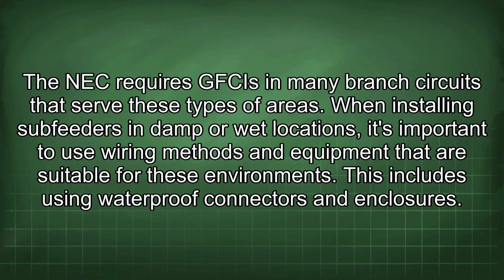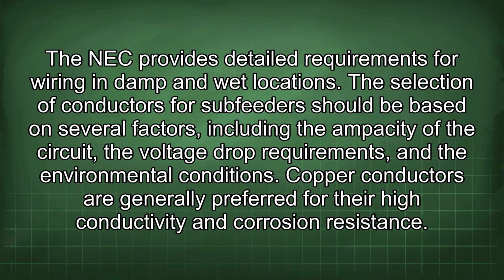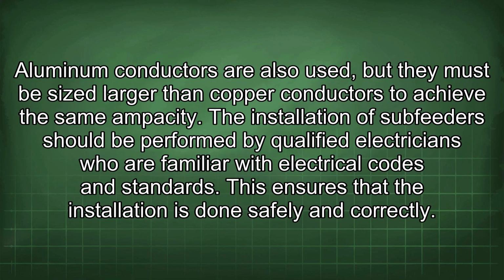When installing subfeeders in damp or wet locations, it's important to use wiring methods and equipment that are suitable for these environments. This includes using waterproof connectors and enclosures. The NEC provides detailed requirements for wiring in damp and wet locations. The selection of conductors for subfeeders should be based on several factors, including the ampacity of the circuit, the voltage drop requirements, and the environmental conditions. Copper conductors are generally preferred for their high conductivity and corrosion resistance. Aluminum conductors are also used, but they must be sized larger than copper conductors to achieve the same ampacity.